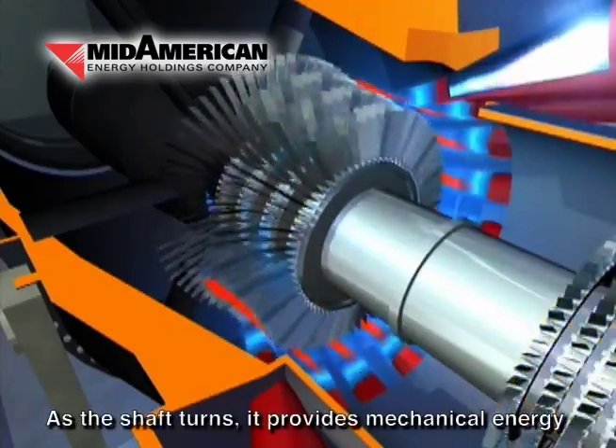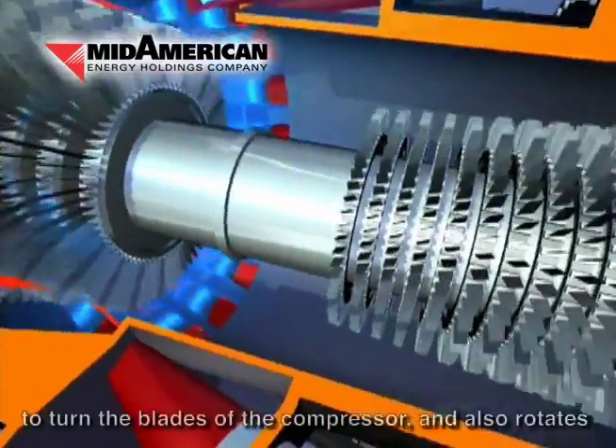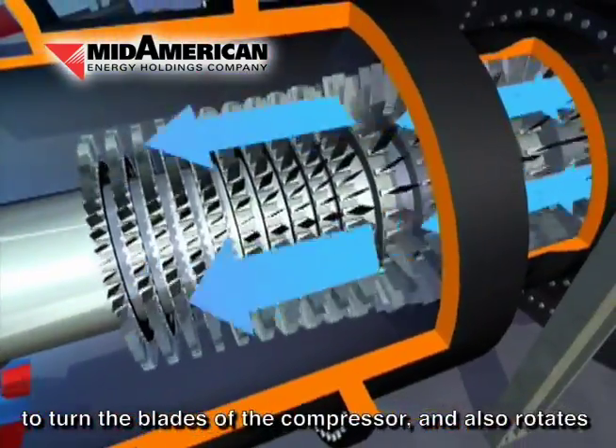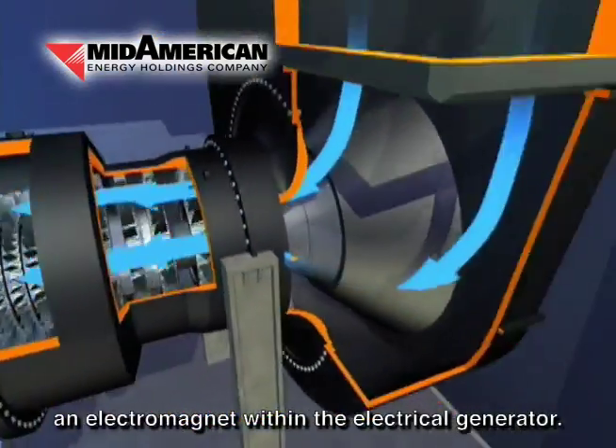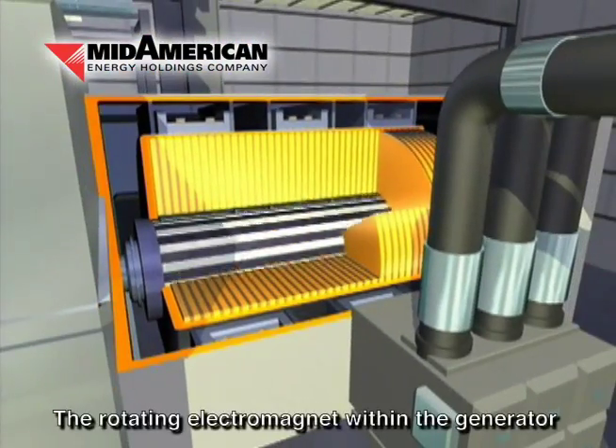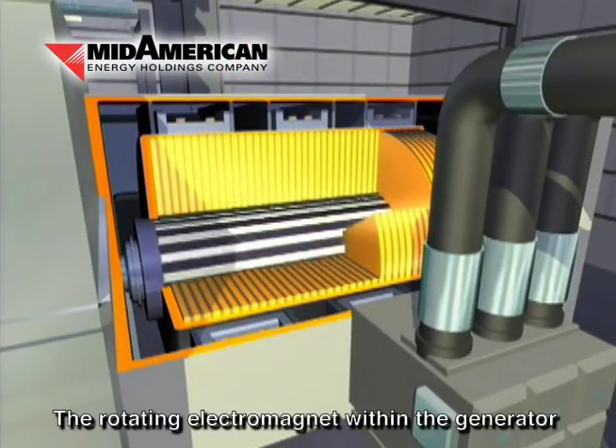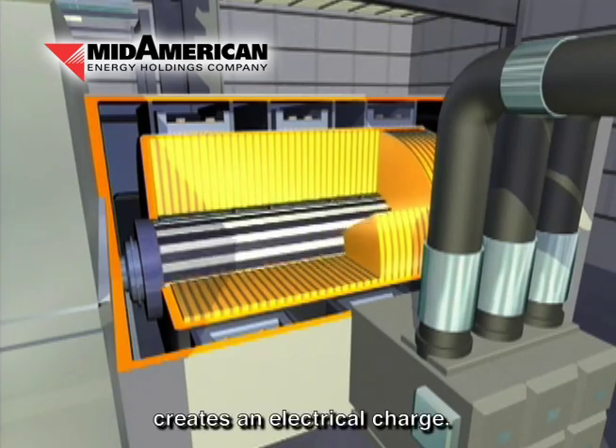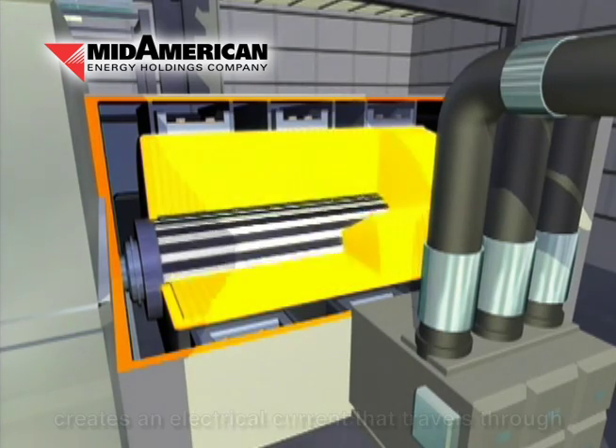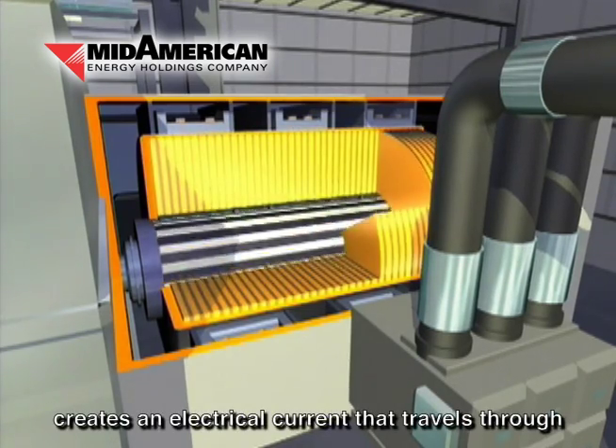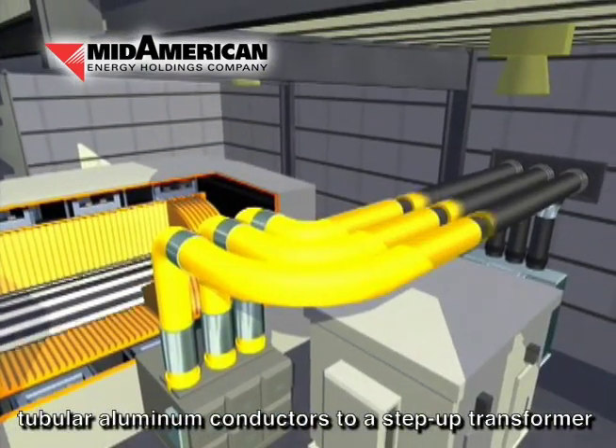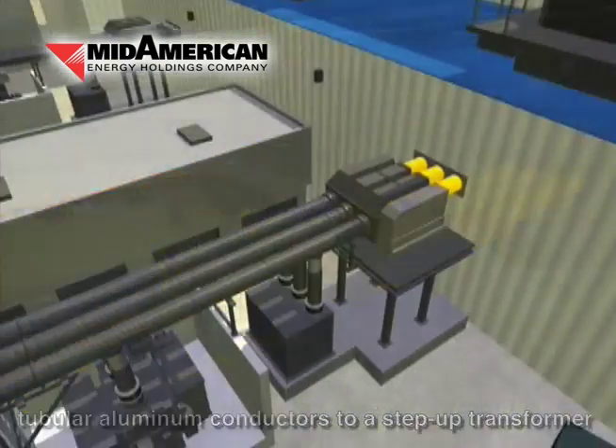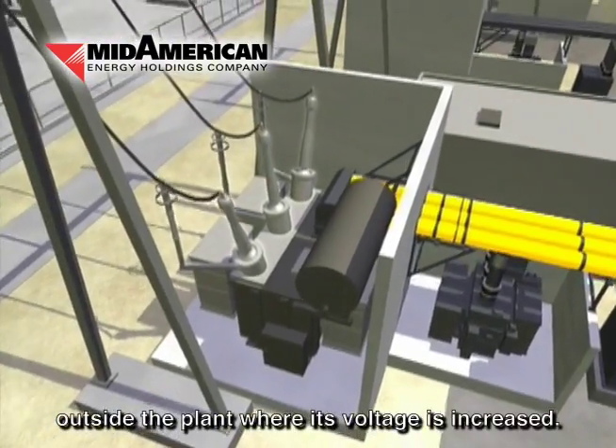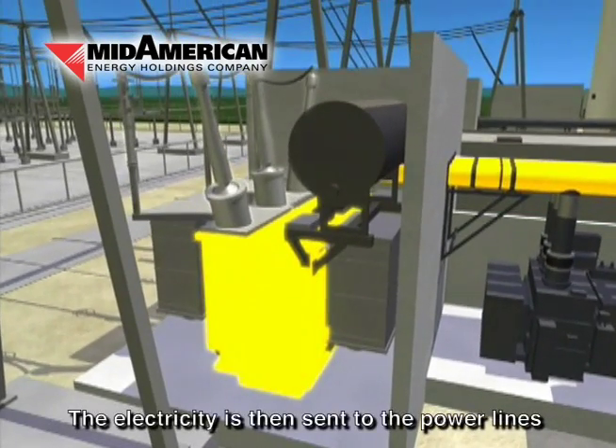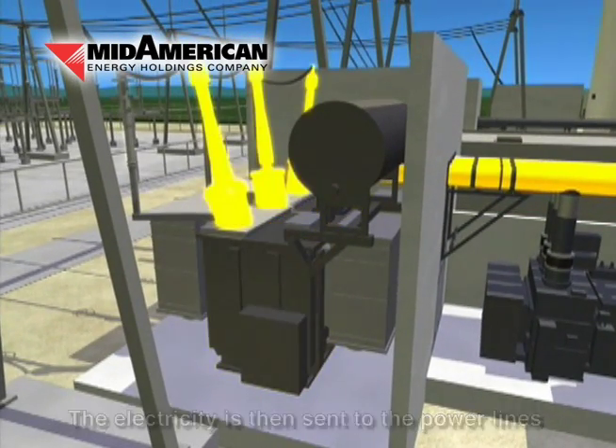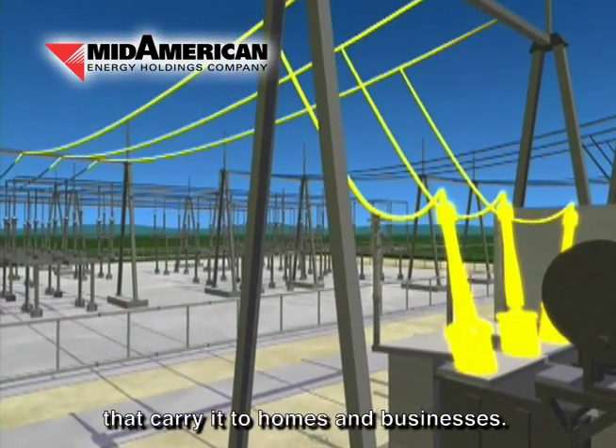As the shaft turns, it provides mechanical energy to turn the blades of the compressor, and also rotates an electromagnet within the electrical generator. The rotating electromagnet within the generator creates an electrical charge. The electrical charge creates an electrical current that travels through tubular aluminum conductors to a step-up transformer outside the plant, where its voltage is increased. The electricity is then sent to the power lines that carry it to homes and businesses.